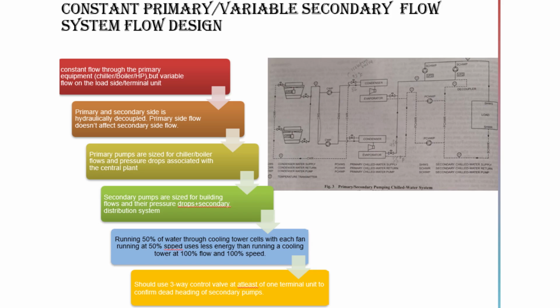As the building load decreases, the secondary pumps slow down, reducing energy consumption. However, the flow through the primary equipment remains constant to ensure stable operation and proper heat exchange performance. When cooling towers are used, operating them at 50% water flow with fans running at 50% speed can use significantly less energy than running at full speed. This highlights the energy savings potential of variable secondary systems. It's also important to use at least one three-way control valve in the system to prevent deadheading of secondary pumps when all two-way valves close.